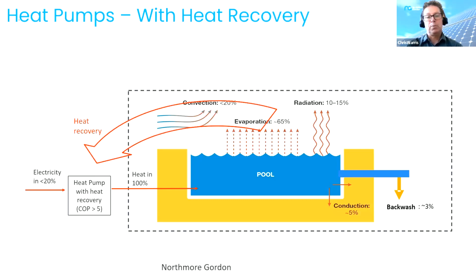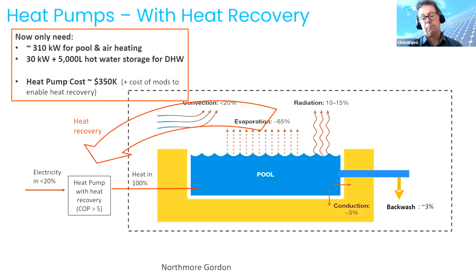Now, all of that heat that's being put into the pool and that you're replacing with your heating system, if it's just leaving the facility, going out to atmosphere, then you just need to keep putting it back in again. But if you can capture some of that heat and reuse it, or use it in your heat pump to make it work better, you can put a smaller heat pump in and it will work more efficiently. So now they only need 310 kilowatts for the pool and air heating, and the heat pump cost goes down to $350,000. This may or may not be practical depending on how much modification you need to do to enable that heat recovery. In some cases it can be relatively inexpensive, but in some cases it can be very expensive and potentially impractical. But in some cases, it can be done.